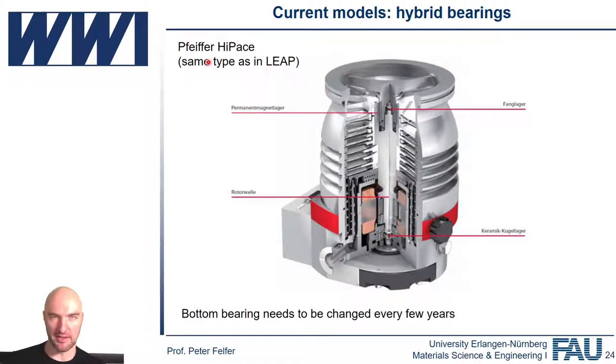This is a modern turbopump, essentially the one that you'll find in the LEAP systems, but also in some of our systems. And you can see here, you've got the initial turbopumping stages, and then you have some stages that are essentially making sure that the pressure here doesn't need to be super, super high in order to get to ultra high vacuum on this side.